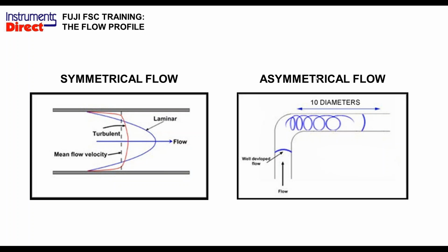Now, an asymmetrical flow profile is basically when you don't have enough straight run of pipe. So in this case, I have my 90-degree elbow. Notice when the flow comes up through this elbow, I have a shorter distance here and a longer distance here, and I'll get a tumbling effect after this. If you were to put your ultrasonic flow meter right here, it would probably go into a fault condition, and you wouldn't get any reading whatsoever.